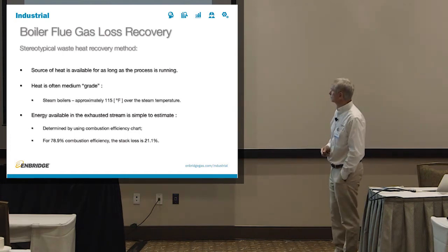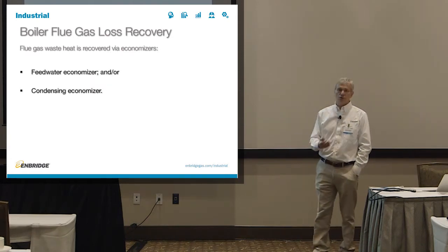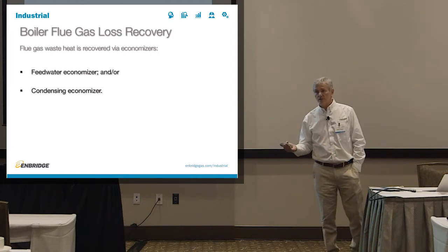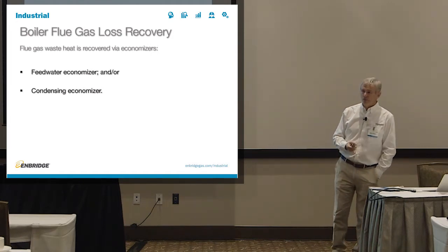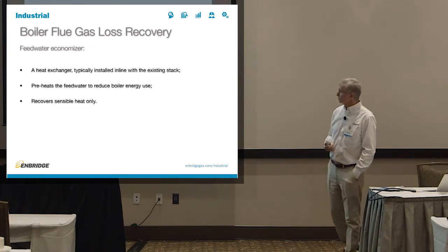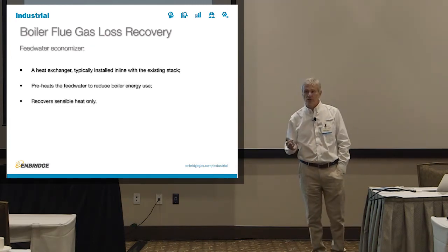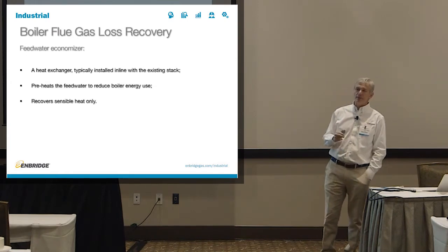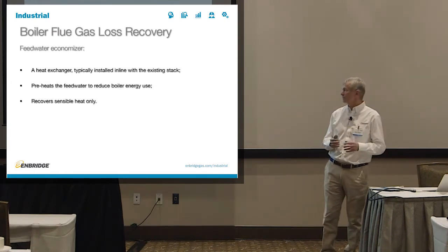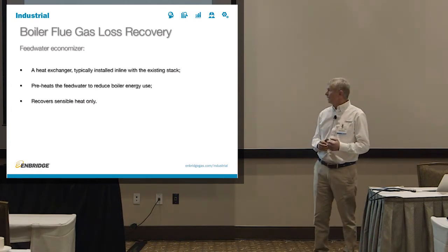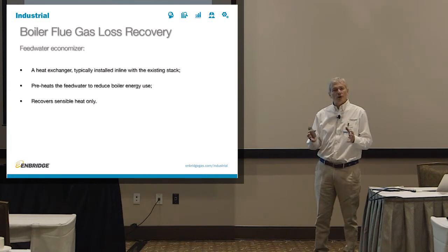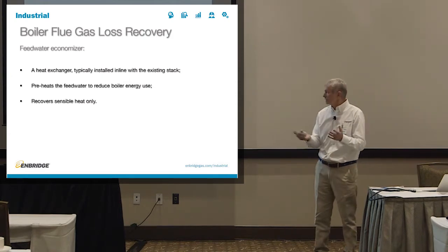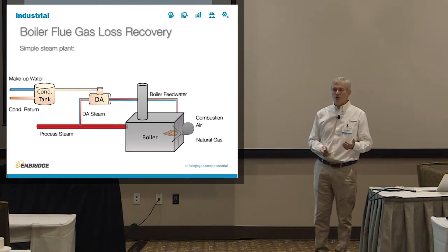It's all the same. So how do you recover it? Most of you have heard of feed water economizers and condensing economizers. We'll see how those work. So a feed water economizer is a heat exchanger. Essentially, that's all it is. It's installed typically within the existing stack, sometimes even within the boiler itself. It preheats the feed water to reduce the boiler energy use, because what the boiler does is take cold water, heat it up to create steam, and then generate the steam. So if you put preheated water into the boiler instead of cold water, the energy the boiler has to generate is slightly less. That's all it does, and it recovers what we call sensible heat only.